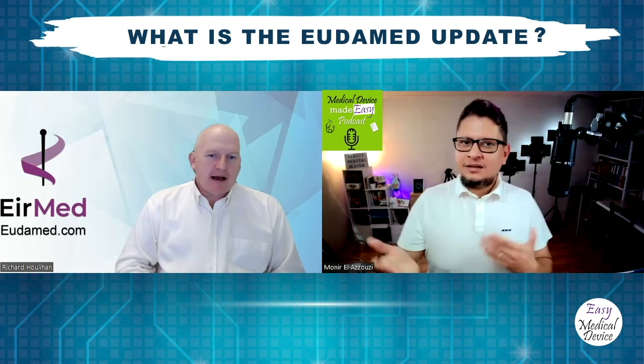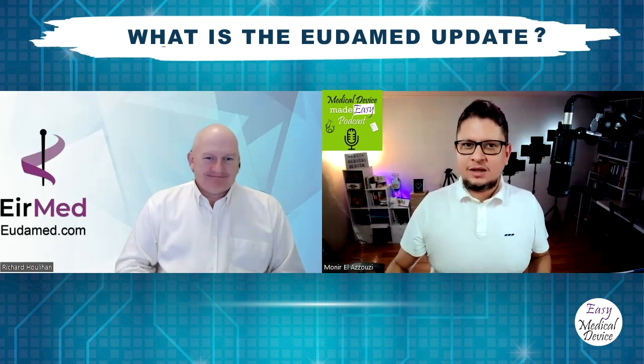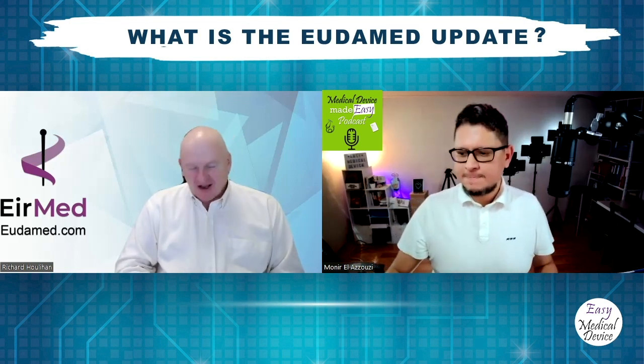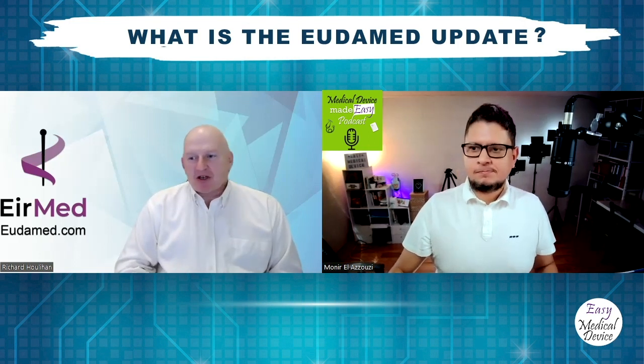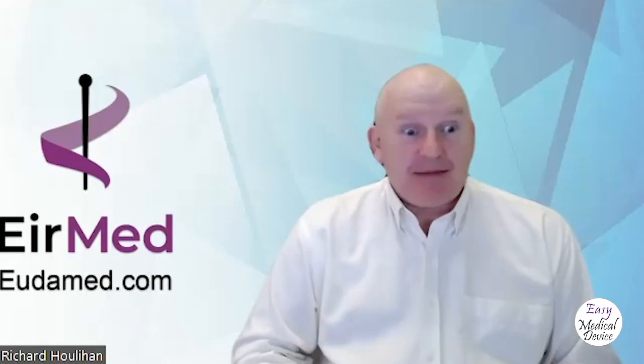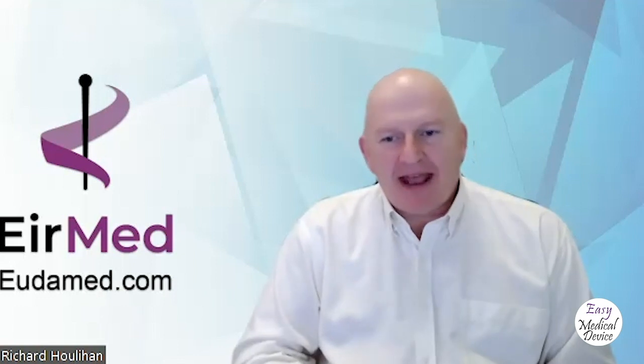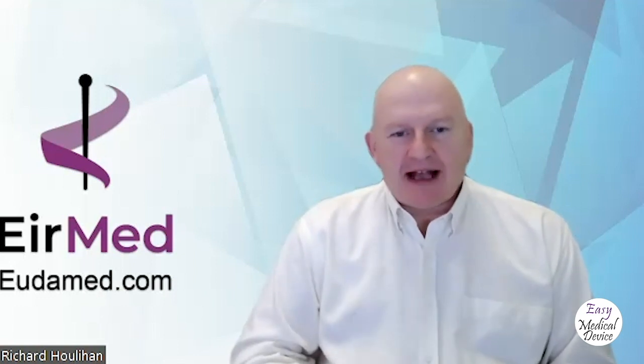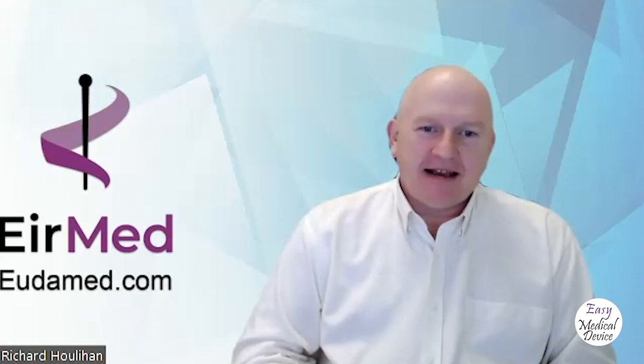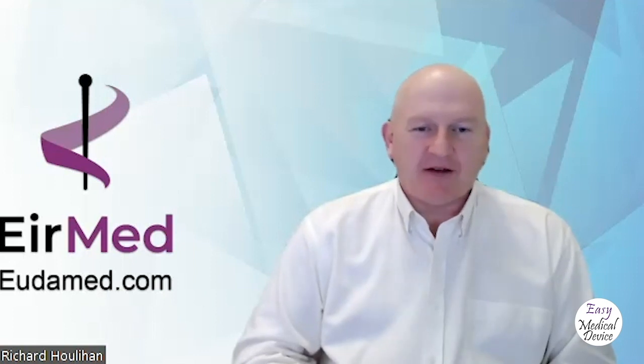So the problem is that we have a lot of customers that contact us and say, Munir, it's been 3 weeks, 4 weeks, 5 weeks, and we still have nothing. Is there an issue? We go to the website and we see, no, it's still under review by the authorities. So is there a solution here, or is there a situation here? Yes, 100%. There are some competent authorities that have decided they are not approving anything until close to when EUDAMED is fully functional.